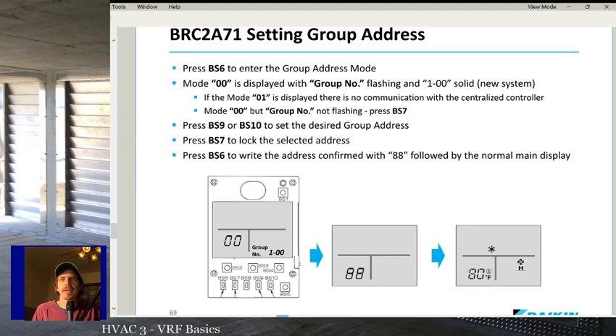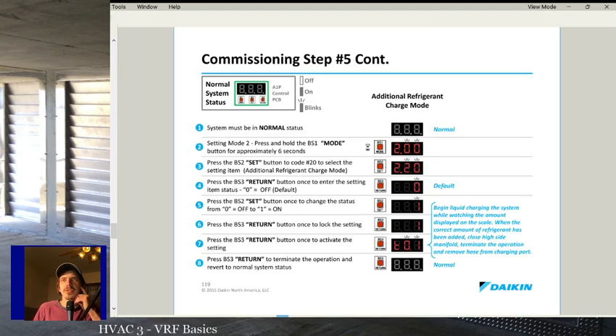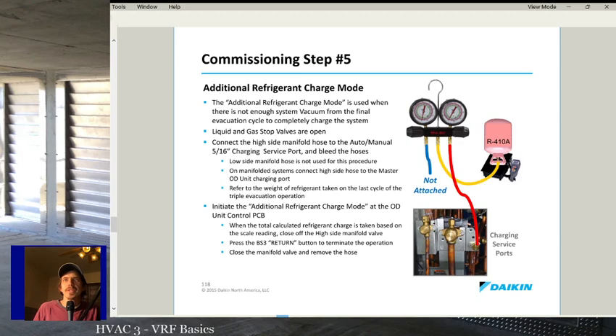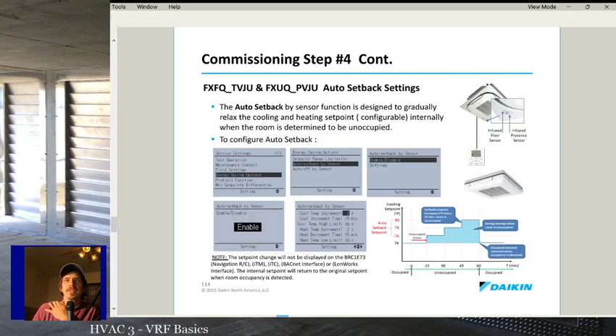And the main reason for that is basically how these units tell which unit it's communicating with, because it's just sending a DC signal to every single unit. Think of it as, and this is probably an oversimplification, but think of it as the outdoor unit, or wherever you're communicating from, is basically testing the resistance or testing the time it takes from when it sends a signal from one indoor unit and when that signal comes back.